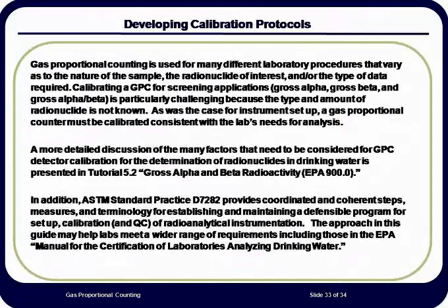Each analysis that is performed may involve different radionuclides. This means different particle energies. It may well be that with your instrument setup, one size does not fit all analyses. You may need to have several different setup and calibration protocols that are written into each radionuclide method to ensure the correct protocol is consistently used. Additionally, it would be good to review ASTM D7282 standard practice, which describes the setup and calibration of newer vintage gas proportional counters and has recommendations on QC checks for the instruments.